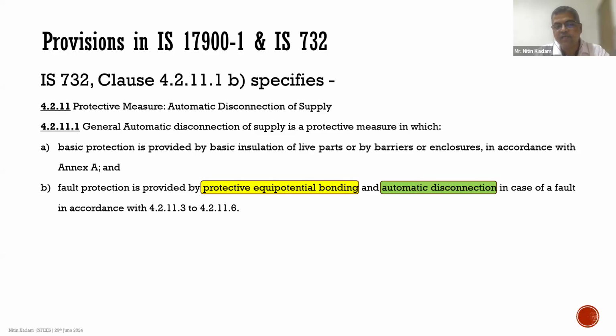But let me specify here that IS 732 is not a new code in India. It has existed for decades. IS 14665 also had a reference to IS 732 and IS 3043, but somehow this code has been overlooked, and this part of protective equipotential bonding and automatic disconnection of power supply has been missed out big time by the elevator and escalator industry. But now IS 17900-1 explicitly specifies that you should have protective equipotential bonding and automatic disconnection of power supply. And in the previous slide, you must have also seen that a fault loop impedance test has to be done. So this is the verification of the equipment on the site by doing certain tests. We'll see those in the subsequent slides.